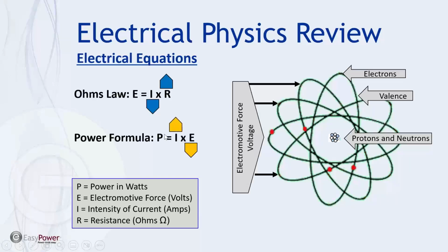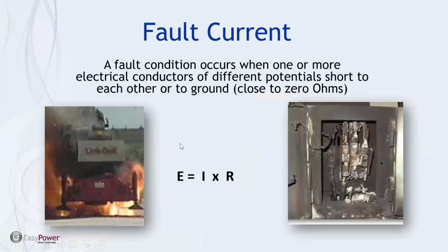So if you've got a certain amount of load somewhere, and you've dropped from 12,000 volts at the power line down to 480 volts in your facility, the current goes up. So you have a lot higher current, and you also would have a higher fault current. And that's also something we're going to be considering as we talk about this. So that's a little bit on electrical basics, and then we'll just move on from there. So let's talk a little bit about fault current.